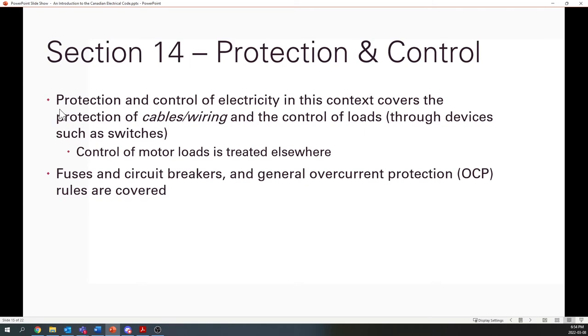Most of us, I'm sure, will be familiar with the circuit breakers in your house and that sort of thing. Fuses are just protective devices that have to be replaced every time they blow. They essentially have a metal element on the inside that is designed to blow when you have too high a current running through it. The circuit breaker does that, except it's resettable. It trips essentially either a thermal or a magnetic element that opens a switch, and then you can reset that.